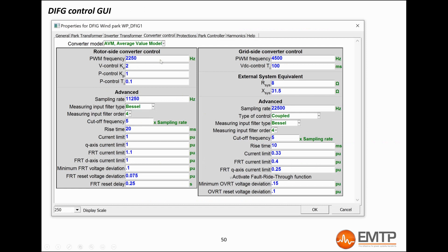The PWM and sampling rate inputs are important only if the converter is modeled in detail with IGBTs. They are not in the case of average value model. The difference between average value model and detail model of inverter will be explained in another video. The type of filter can be varied. It can have an influence on certain studies like subsynchronous control interaction, but are of minor importance for most studies, so you don't really have to worry about it.